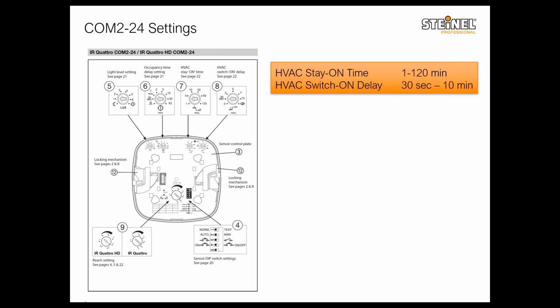So what do these two mean? What is their setting and how should we treat them? Stay on time can be adjusted between 0 and 120 minutes. 0 is for when we don't want to use it, so 1 to 120 minutes is your adjustment range if you are planning to use it. This is the period of time that the contact will be closed or open, depending on the normally open or normally closed side that you want to use, after the last occupancy. So when the sensor does not detect any more occupancy, the countdown timer, depending on the setting, let's say 60 minutes, will start counting down, and then it will release that relay.